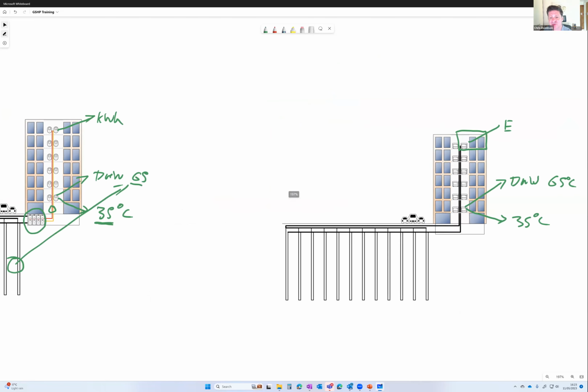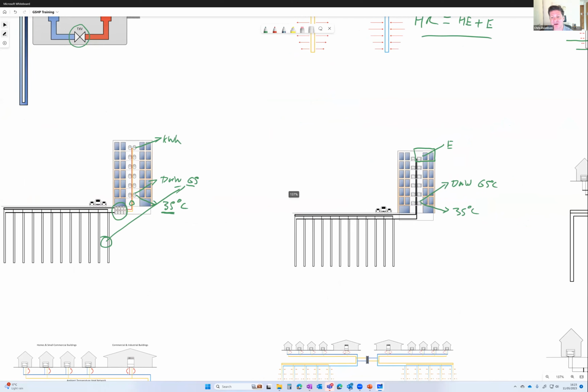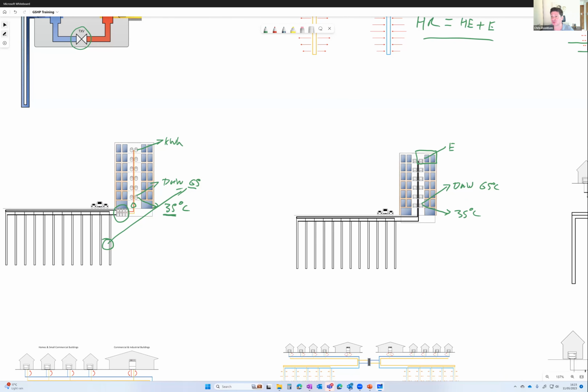So we've got two contrasting solutions here, with different engineering and commercial aspects. Technically, almost always the more efficient system tends to be this one, because of that flip between domestic hot water and space heating. However, the network might not get built without that kilowatt hour sale of heat. So we do feasibility studies comparing both, and it comes down one way or the other - it doesn't always favour the more efficient solution, depending on the commercials of the project.